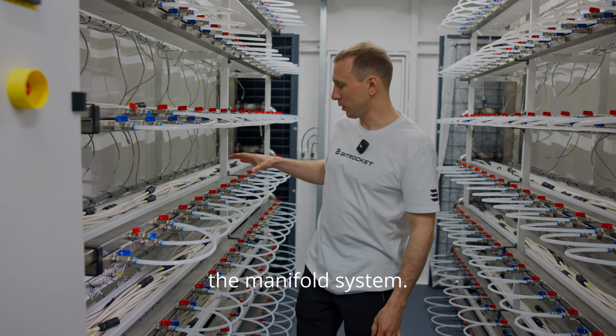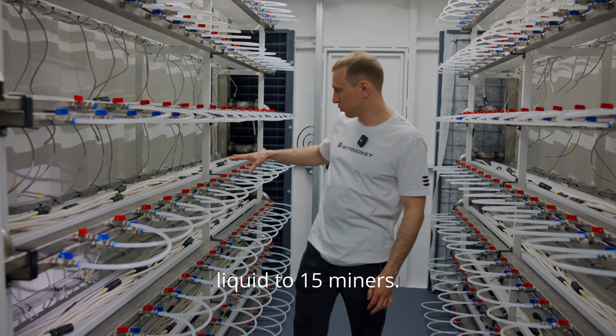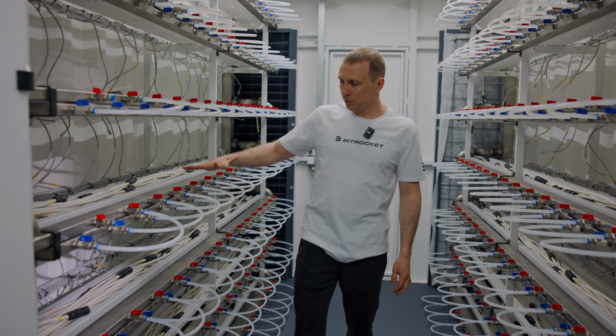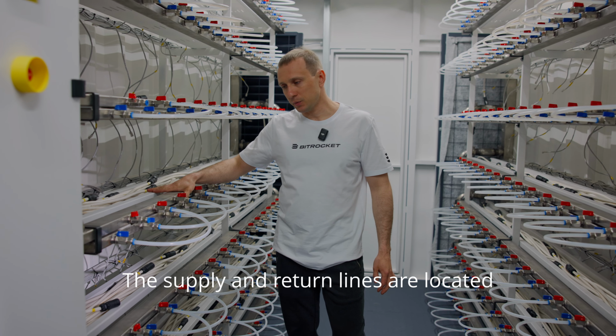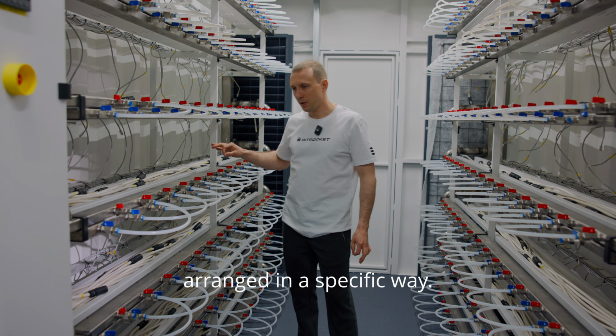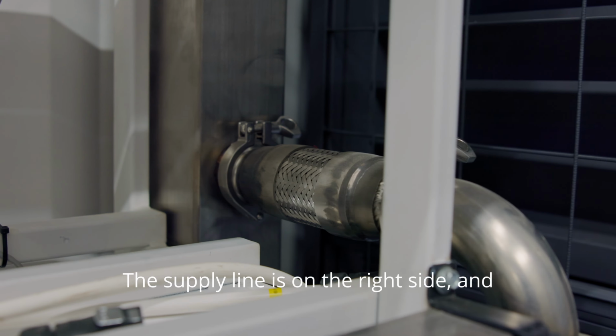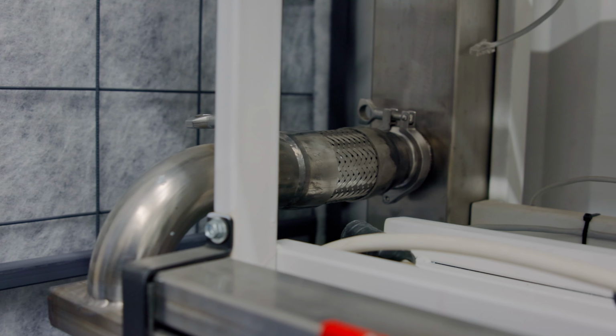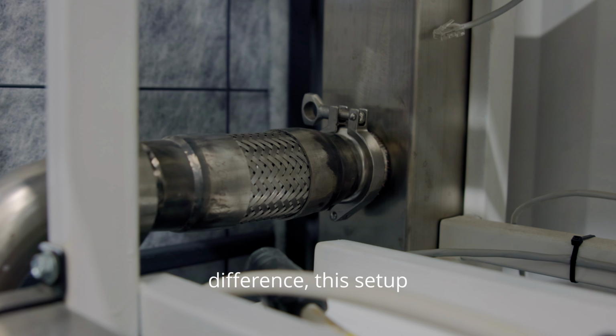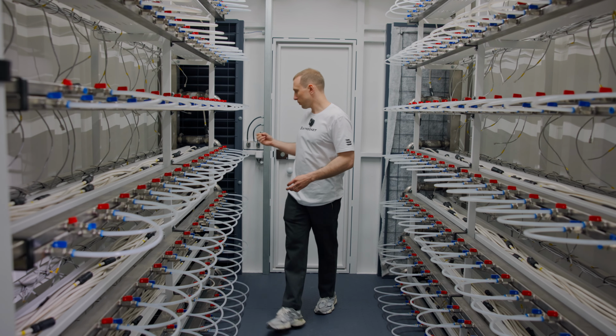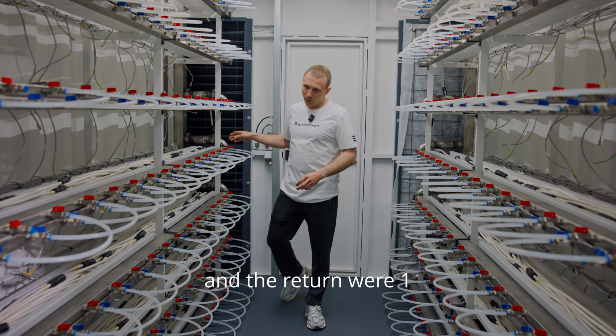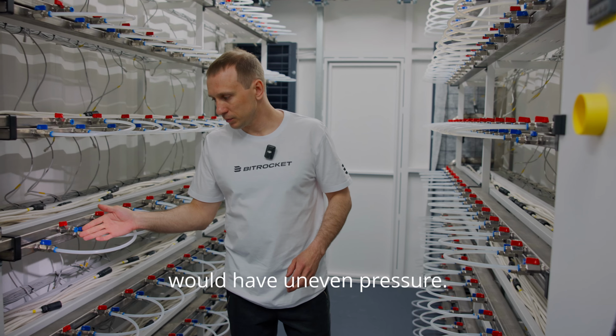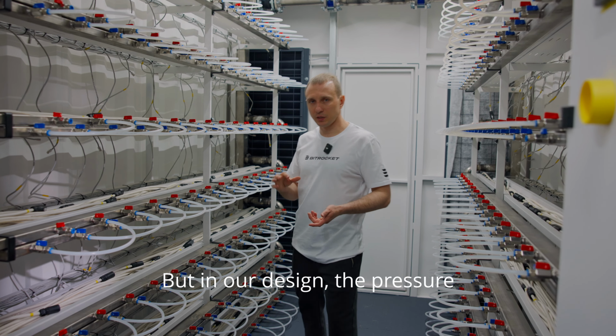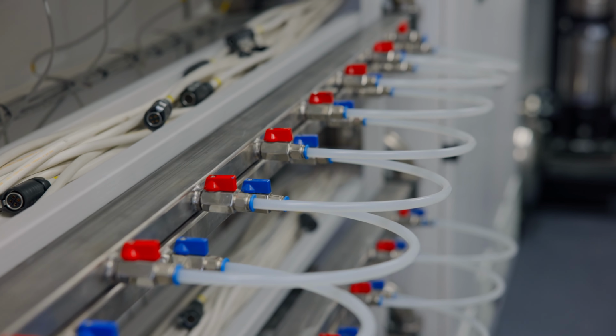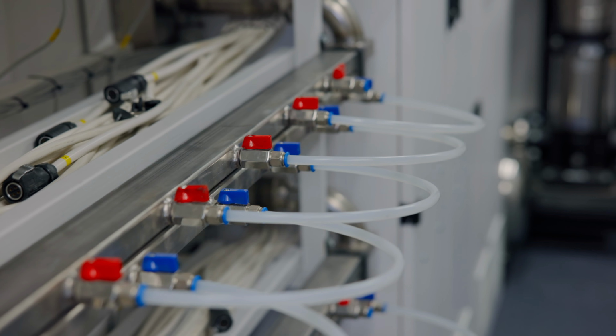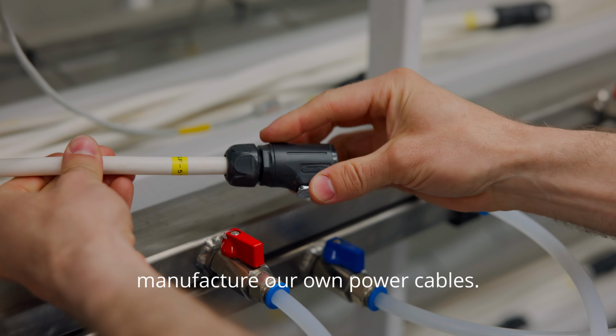The next component is the manifold system. One manifold supplies liquid to 15 miners. Pay attention. The supply and return lines are located underneath the miners, arranged in a specific way. The supply line is on the right side, and the return line is on the left. Due to hydraulic resistance and pressure difference, this setup ensures that each miner receives equal cooling. If the supply pressure here were 3 bar and the return were 1 bar, the miners at the ends would have uneven pressure. But in our design, the pressure differential remains consistent across all units, so the flow rate through each miner is uniform.